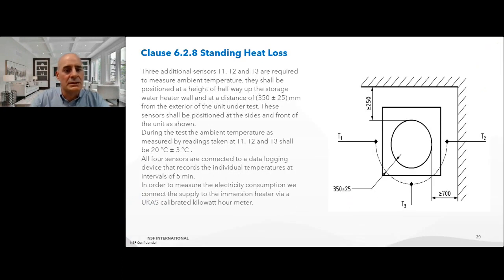Three additional sensors, T1, T2 and T3, are required to measure the ambient temperature. They should be positioned at a height of halfway up the storage water heater wall and at a distance of 350 plus or minus 25 millimeters from the exterior of the unit under test. These sensors should be positioned at the sides and front of the unit as shown. So you can see them there, T1, T2, T3, positioned around at the correct height and distance away. During the test, the ambient temperature as measured by the readings taken at T1, T2 and T3 should be 20 degrees plus or minus 3 degrees.